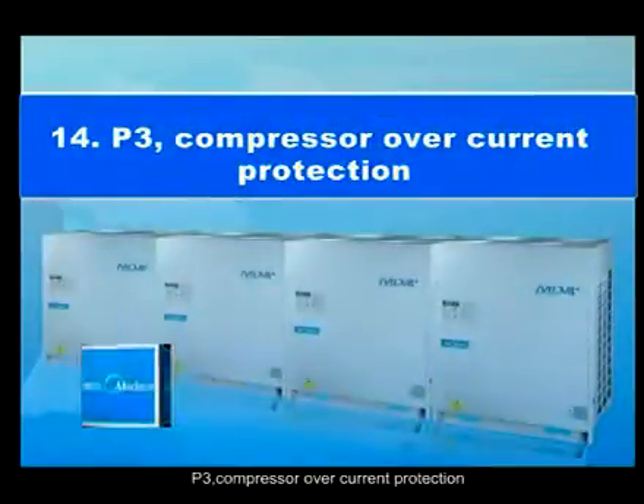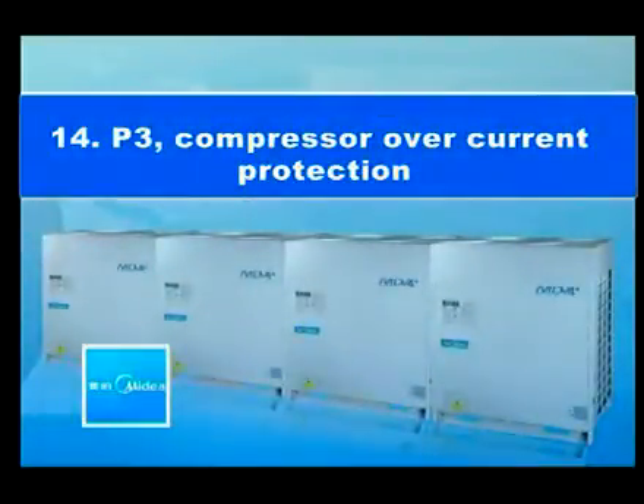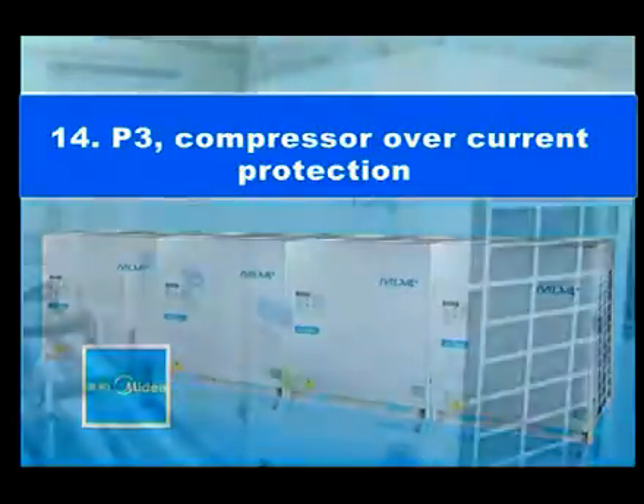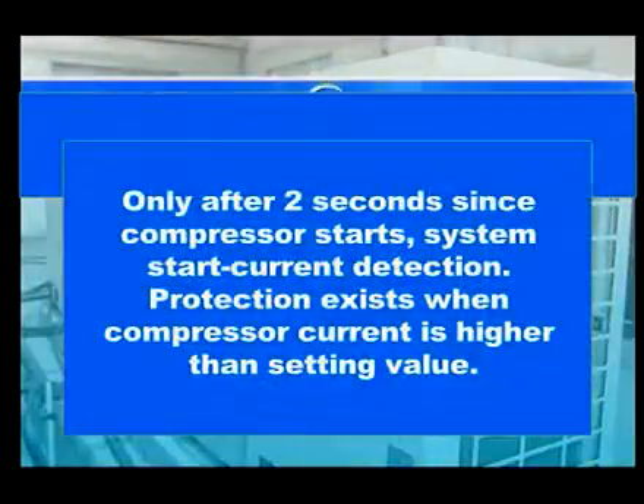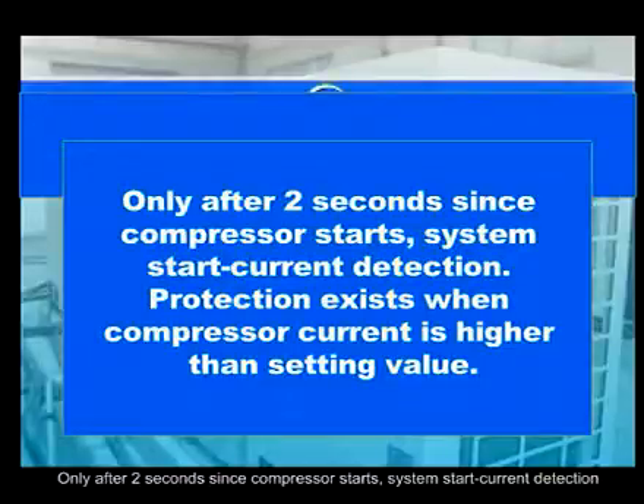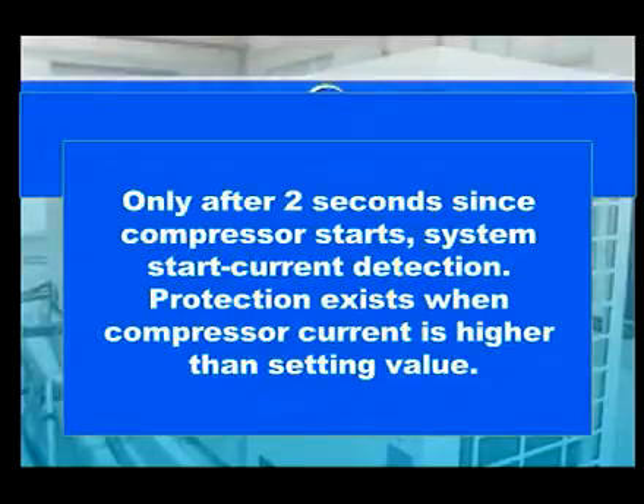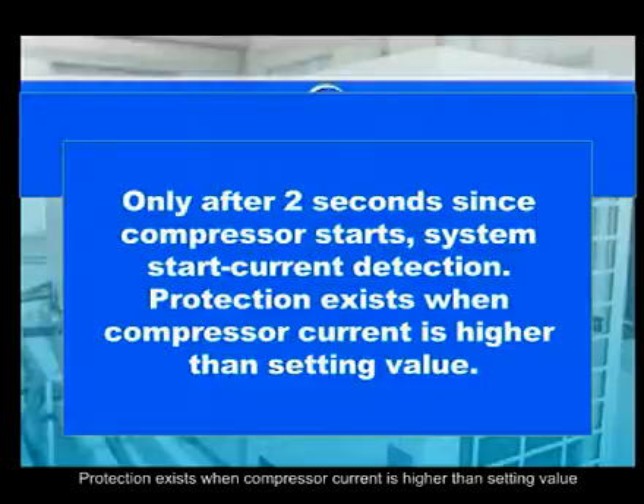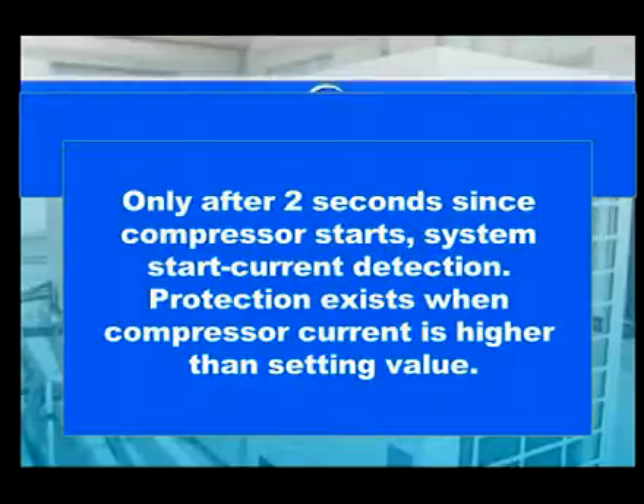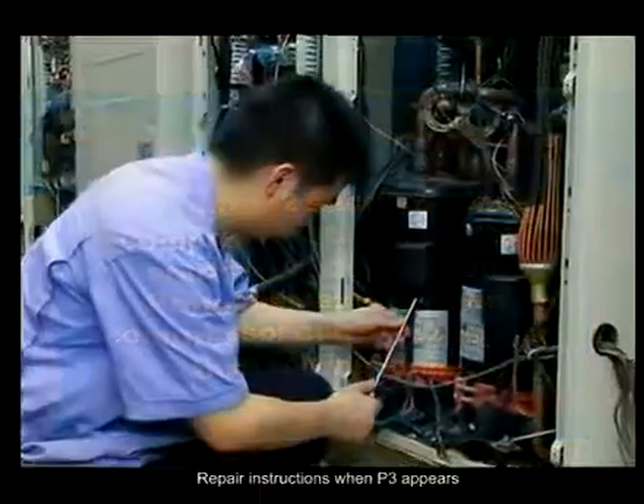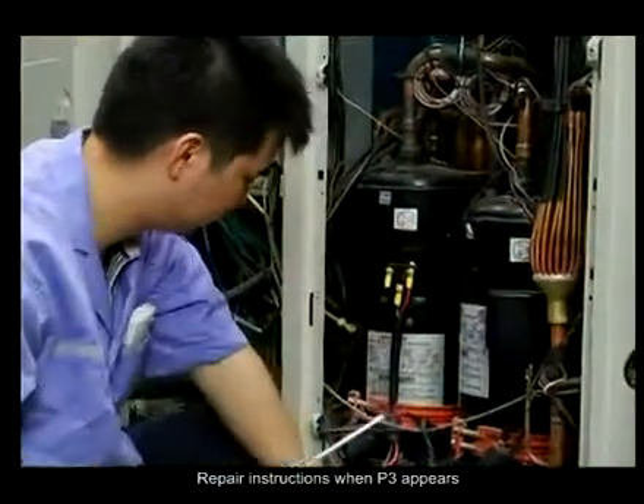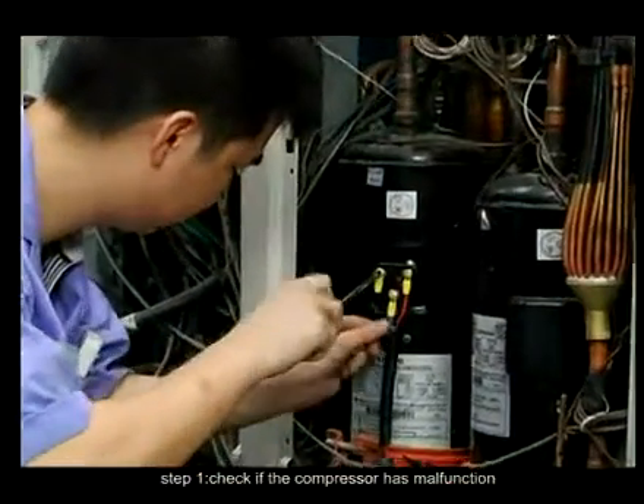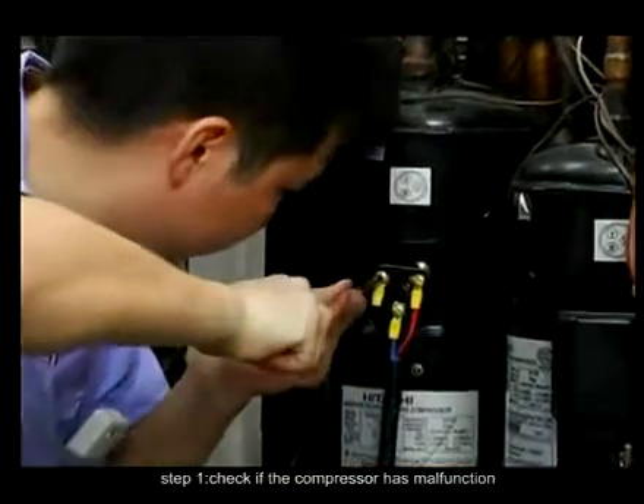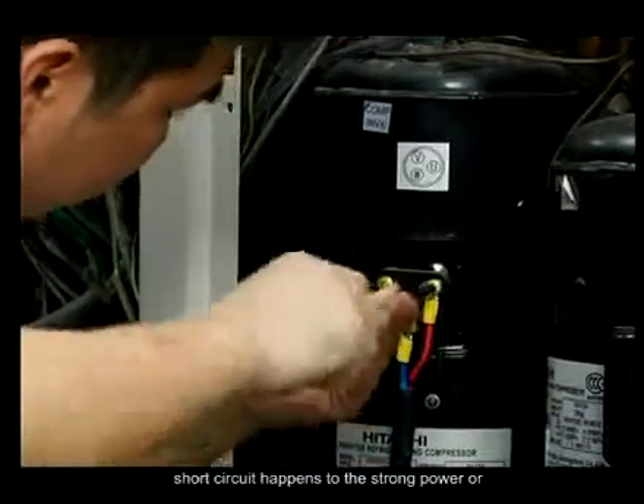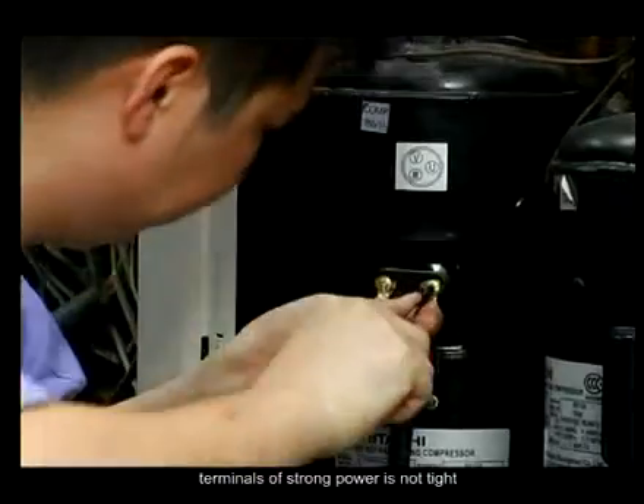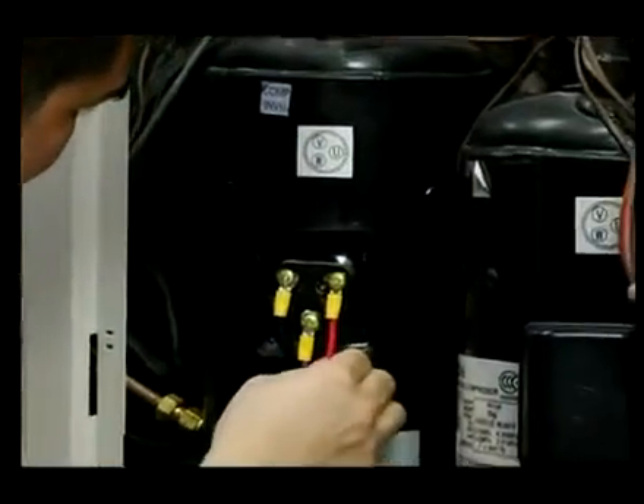P3. Compressor over current protection. Only 2 seconds after the compressor starts, the system starts current detection. Protection exists when the compressor current is higher than the setting value. Repair instructions when P3 appears. Step 1. Check if the compressor has a malfunction, a short circuit, or if the strong power terminals are not tight.